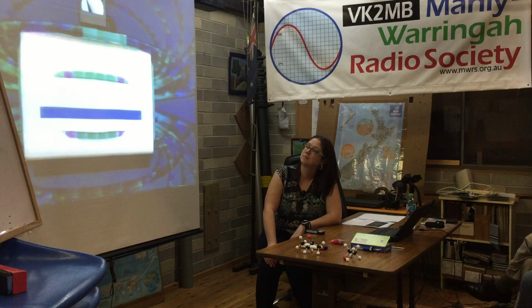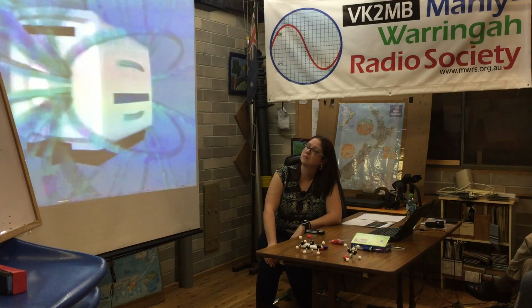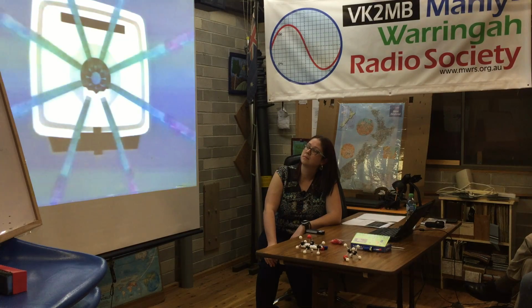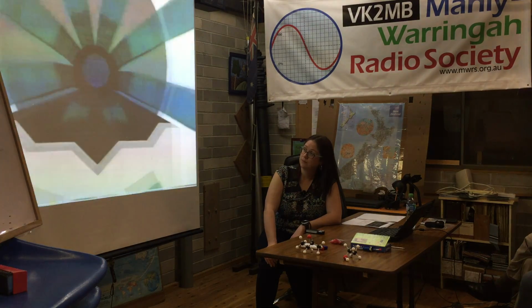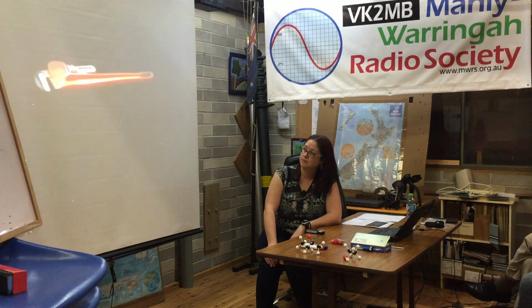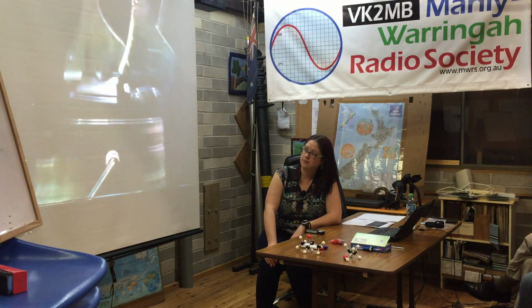The MR magnetic field shape is the same as that of a bar magnet, pulling with the greatest force where field lines converge. And as with any magnet, the closer you are, the greater the magnetic force. How strong is the force? How would it affect some of the tools and other objects that might be accidentally brought into an MR scan room?